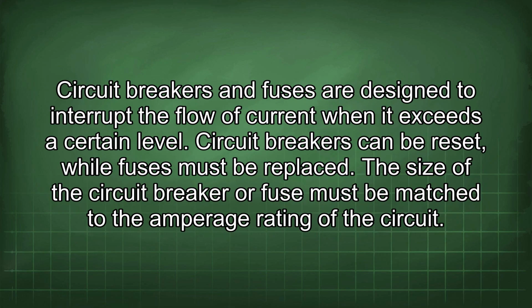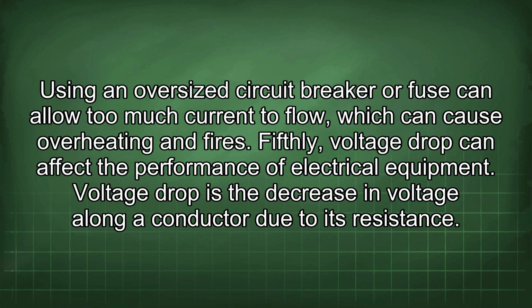Fourthly, overcurrent protection is critical for preventing fires. Circuit breakers and fuses are designed to interrupt the flow of current when it exceeds a certain level. Circuit breakers can be reset while fuses must be replaced. The size of the circuit breaker or fuse must be matched to the amperage rating of the circuit. Using an oversized circuit breaker or fuse can allow too much current to flow, which can cause overheating and fires.